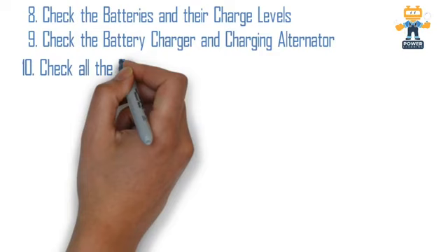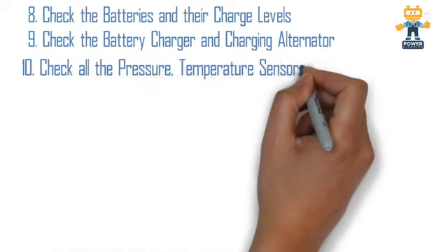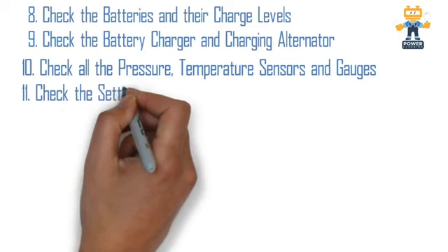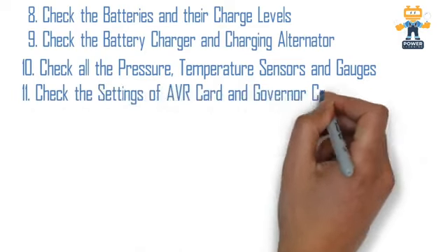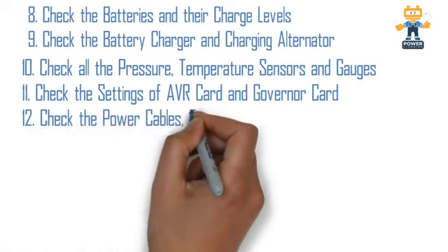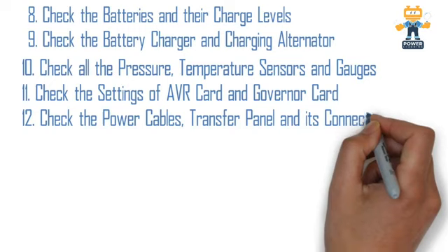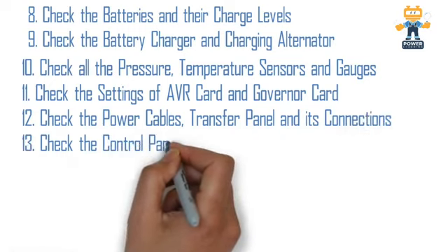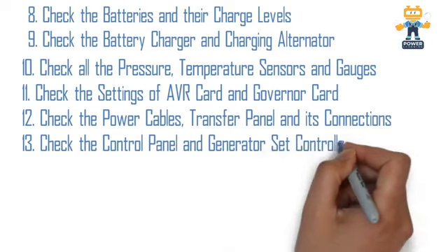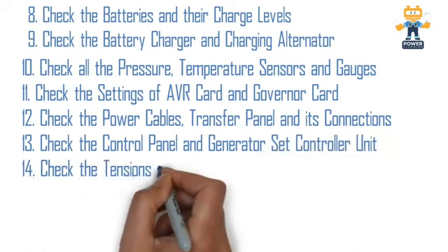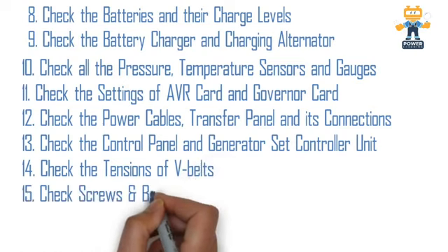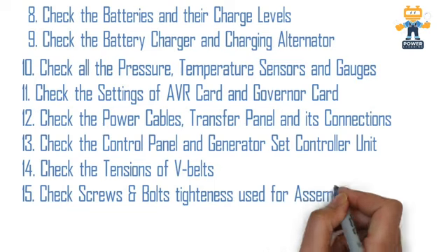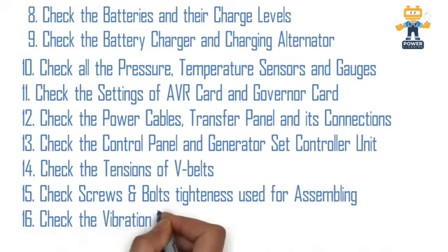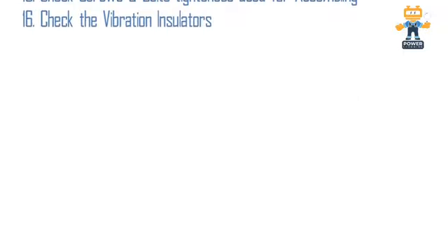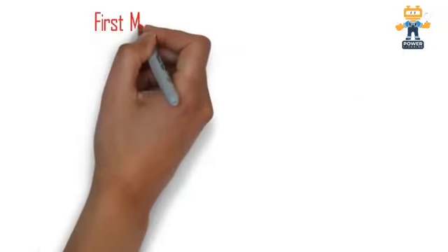So this is our complete list. For number 10, we also have to check all the pressure and temperature sensors and gauges while the generator is running. Check the settings of the AVR card and governor card. You have to check the voltage and the engine speed while the generator is running. Check the power cables, transfer panel and its connections before starting, and check the control panel and generator set controller unit while the generator is running and before running. Check the tension of the belt while the engine is in stop mode, check the tightness of the screws and bolts used for assembly before starting, and check the vibration isolators. These are the very important points before startup and for a new genset startup.